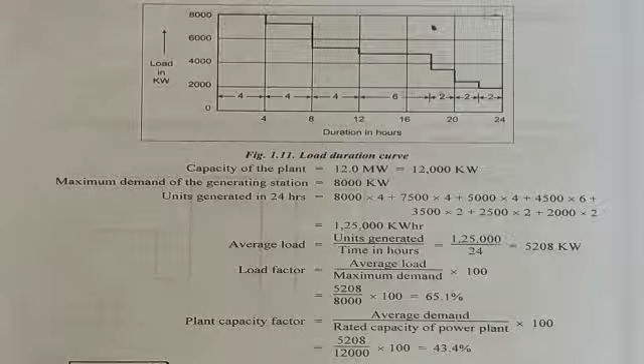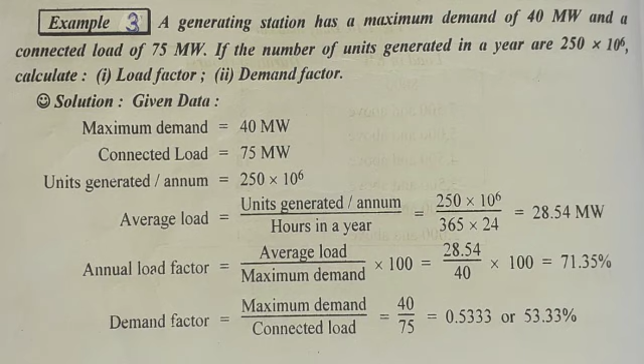In this problem, a generating station has a maximum demand of 40 megawatt and a connected load of 75 megawatt. If the number of units generated in a year is 250 into 10 power 6, calculate load factor and demand factor. Here maximum demand, connected load, and units generated per annum are given. First calculate the annual load factor, average load divided by maximum demand into 100. First calculate average load, units generated per annum by hours in a year, which is 28.54 megawatt. Annual load factor is 71.35%. Demand factor is equal to maximum demand by connected load, equal to 53.33%.